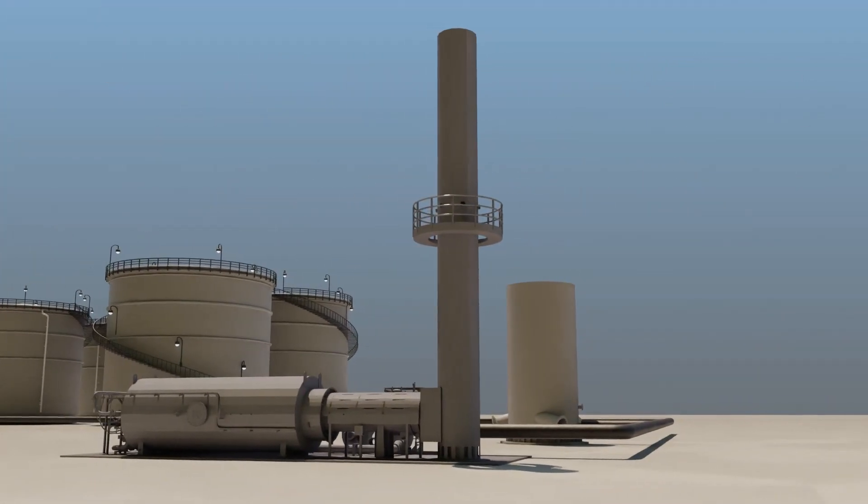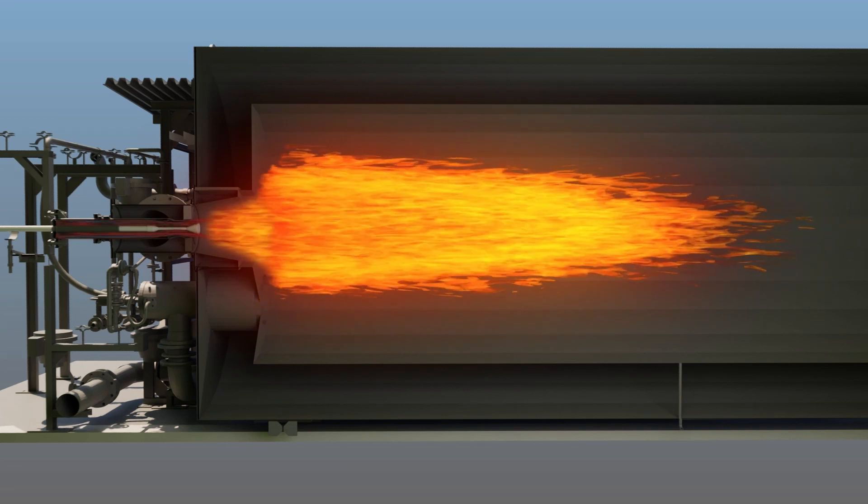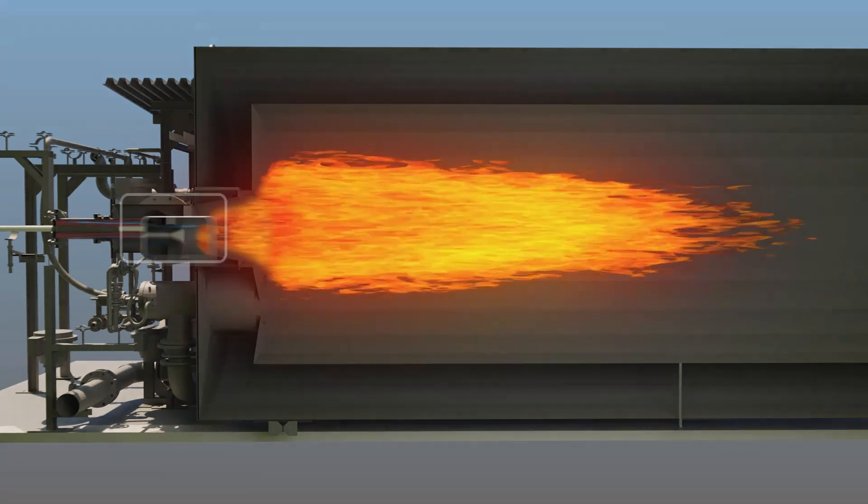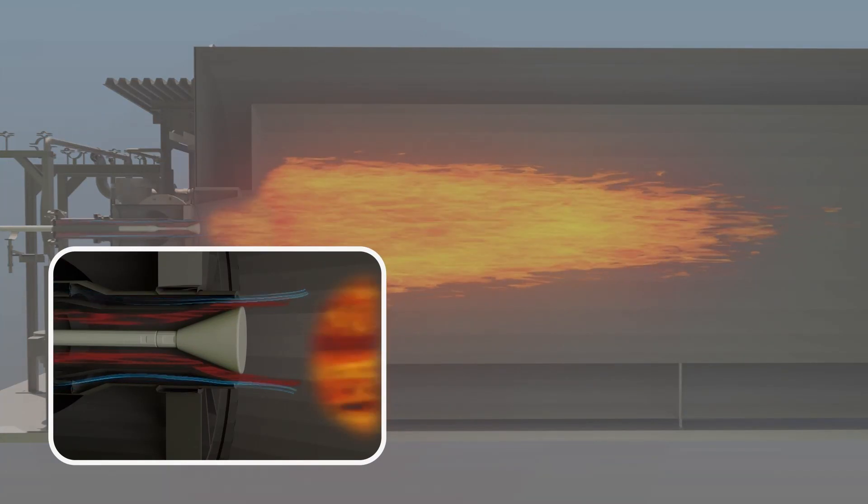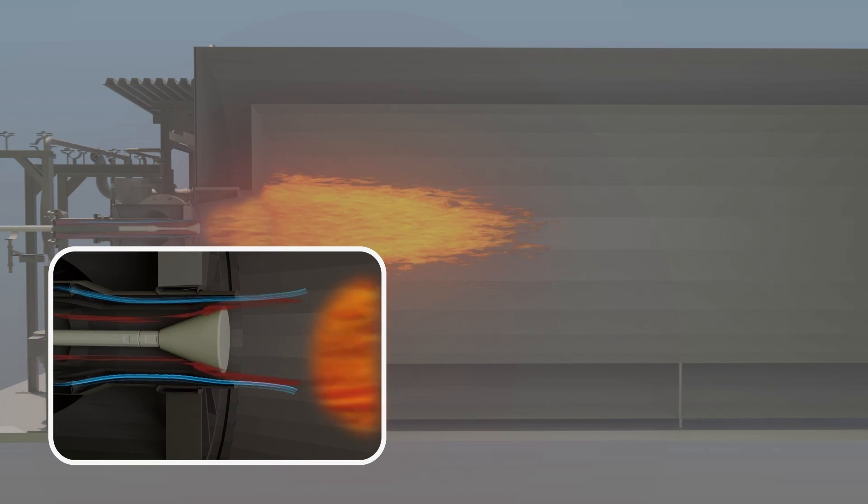Dumag developed a concept with a revolutionary economic new way to dynamically inject vapors into the oxidizer. If the vapor flow rate is reduced, the Dumag burner head automatically adjusts its position and reduces the cross section of the vapor outlet.